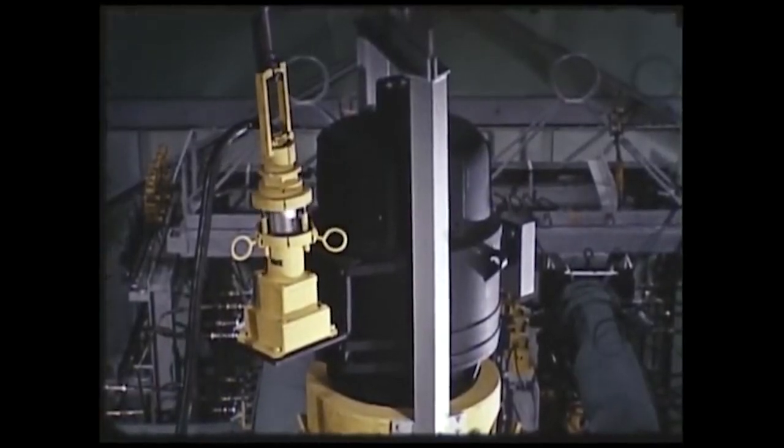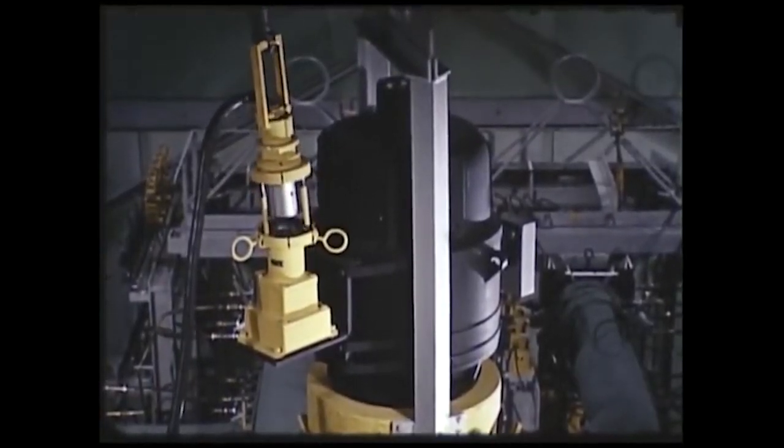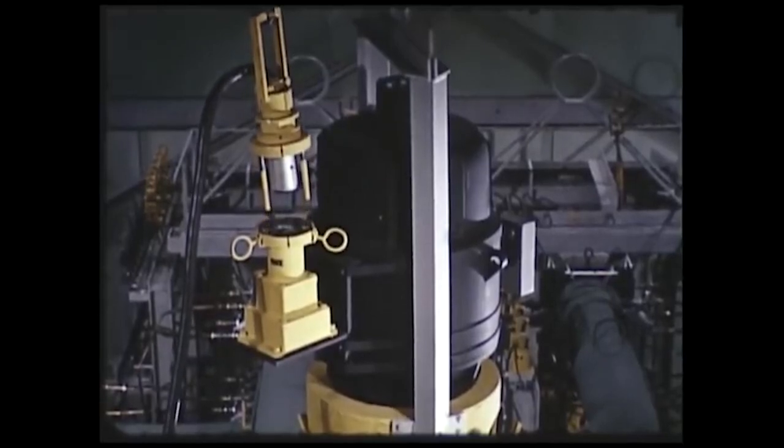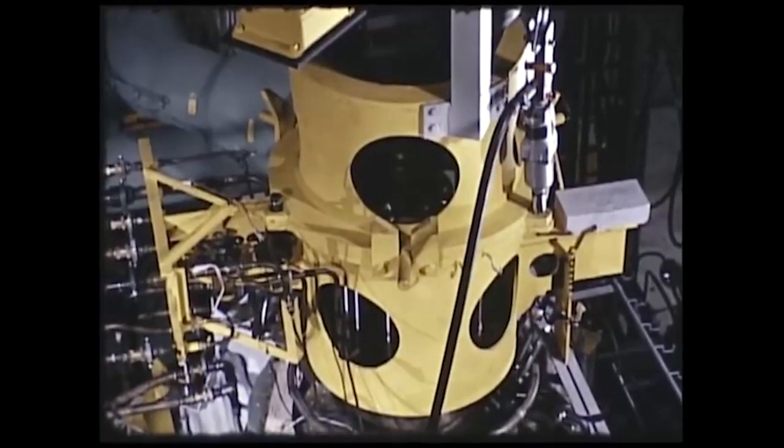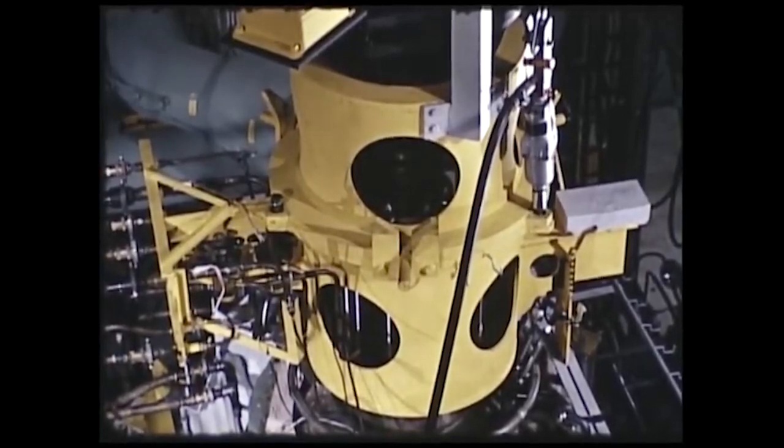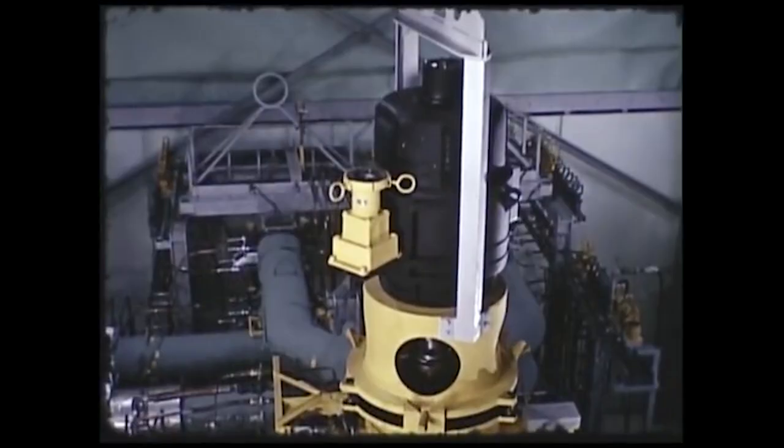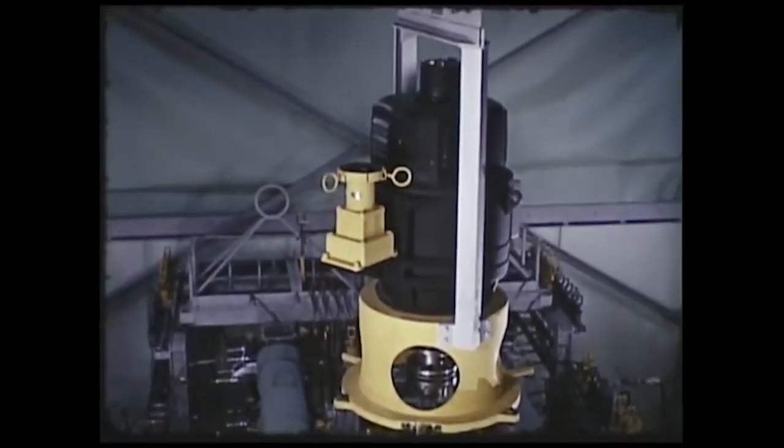In removing the motor, pump, and reactor, the motor is first disconnected electrically by the remote manipulator. Three bolts holding the motor and pump spool units together are loosened with a pneumatically operated impact wrench. The motor is lifted from the pump and removed from the cell.